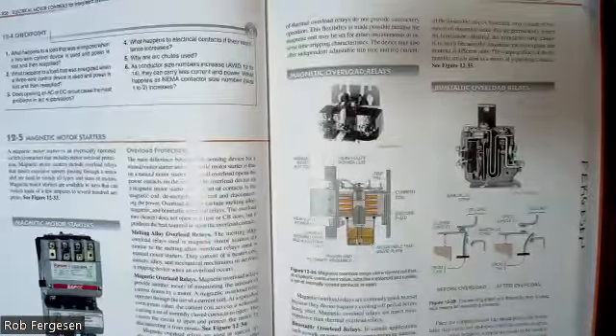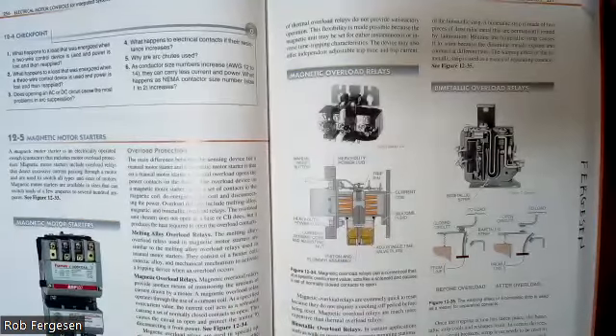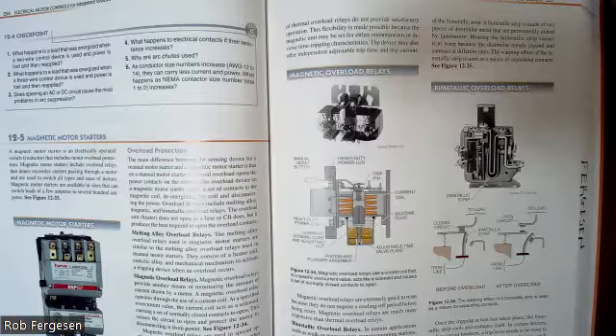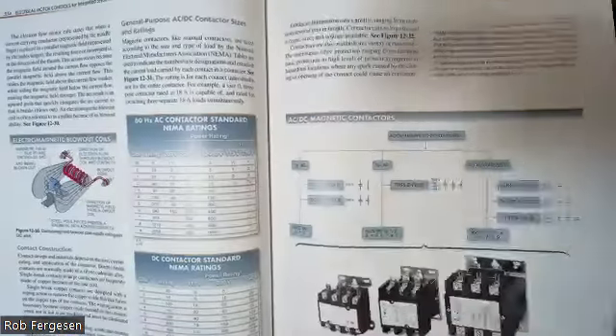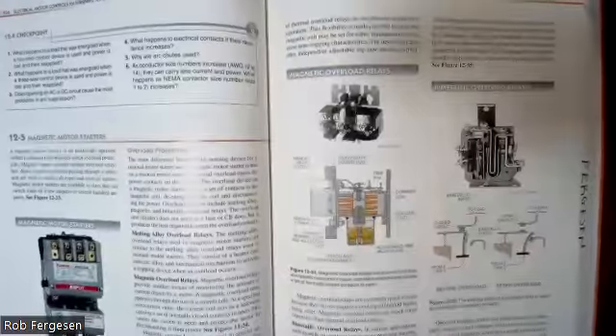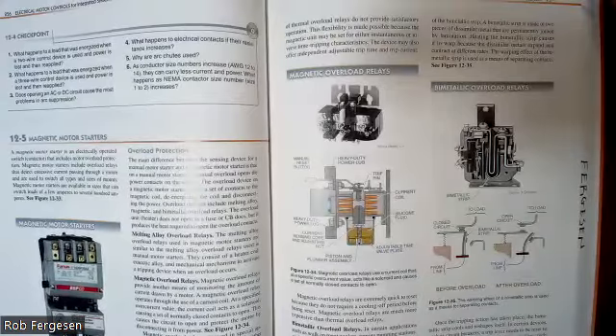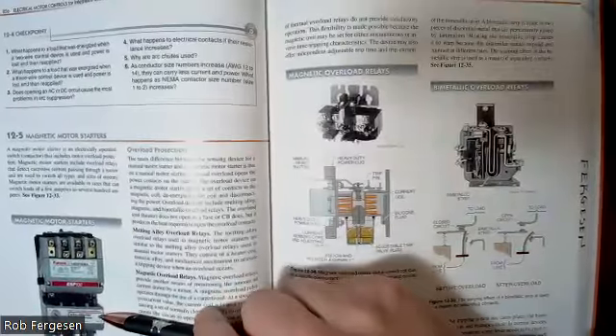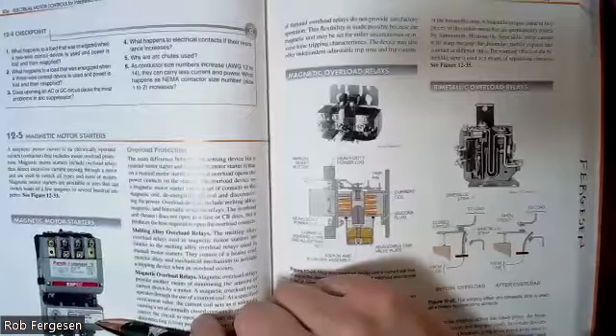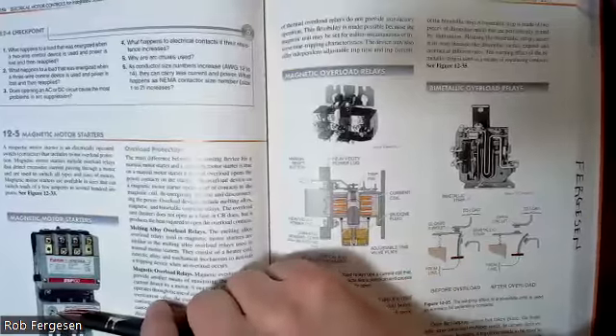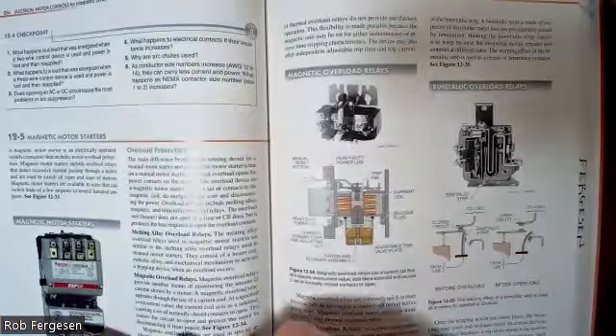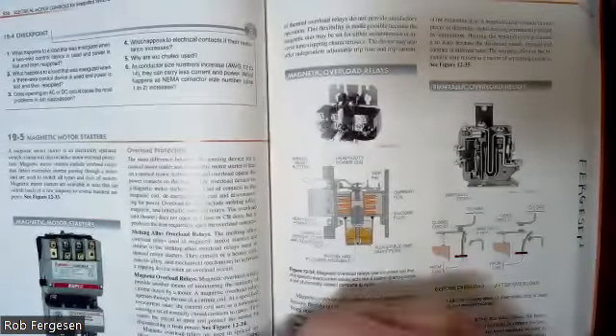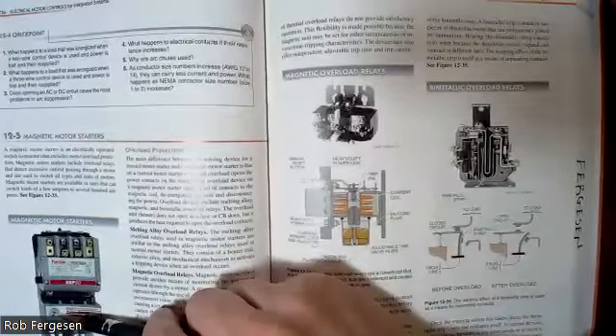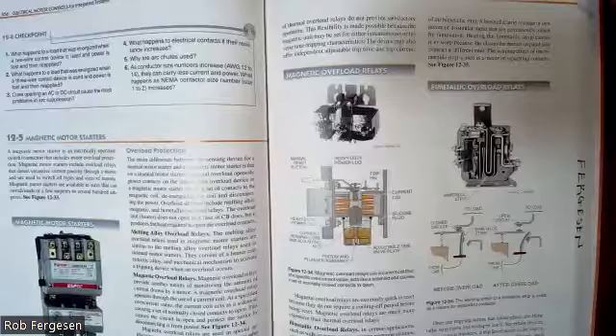So kind of bridging over to the next level, on 12.5, we get into the meat and potatoes for the controls industry, which is magnetic motor starters. So the only difference between a contactor and a magnetic motor starter is, of course, the overload protection. This is a classic magnetic motor starter with overload, and the overload in this case is the electronic overload with the dial-o-matic. Obviously it's not called that, I just use that word, current. So you buy these single motor starters. They can handle a range of different motors, and you have to make sure you select the right current to match the current that you are going to be wiring the motor up to.